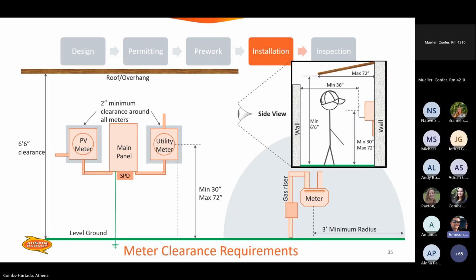Okay, so a diagram of working clearances. We always have full headroom above. We have to have 2 inches around each meter. And then we have to have 30 inches to the center minimum and a maximum of 72 inches. I did see one yesterday that was at about 76 inches to center. Basically, if you're about 5'6" to 6 feet tall, just no meters above our heads. I've always kind of looked at it that way. And then within 3 feet of a gas riser, gas meter, or gas regulator. Next slide, please.